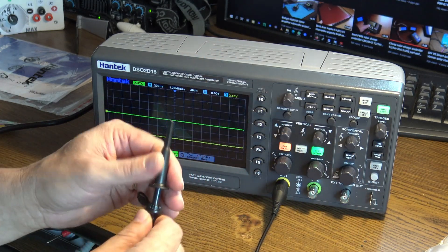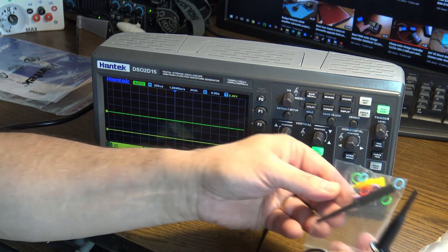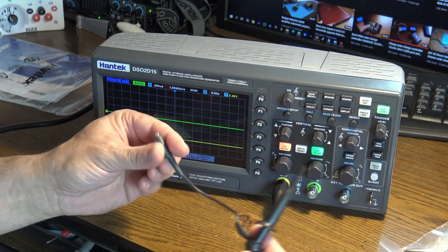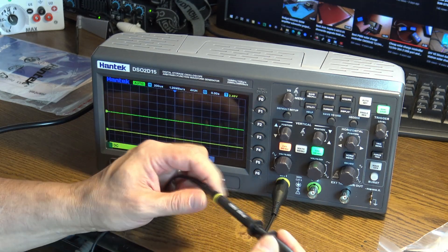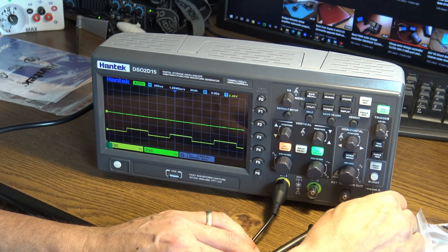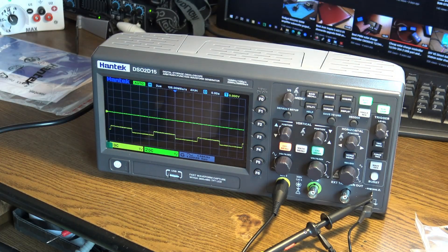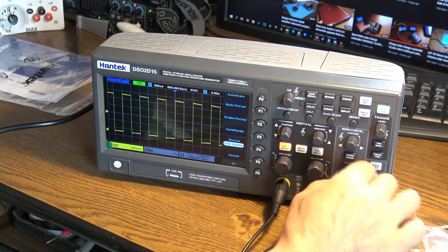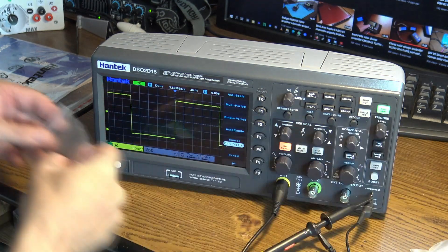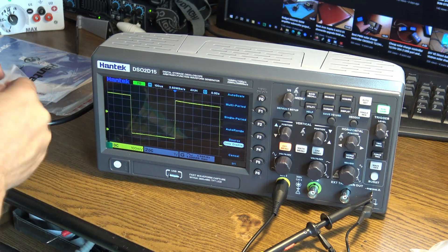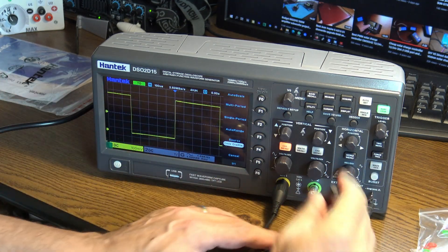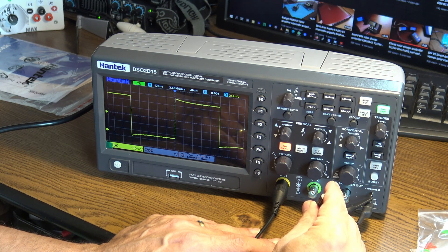This is a 150 megahertz oscilloscope, beautiful. Let's see about calibration. Let's make this a little better, just a little over. It needs calibration, just a little bit. Let's fix it, it's very easy to do that.